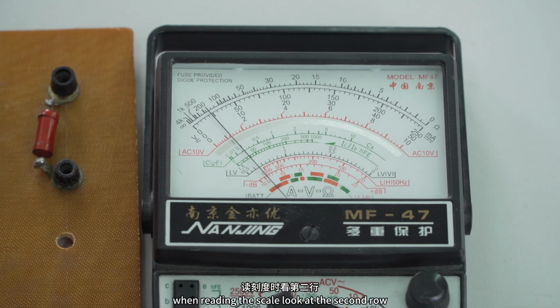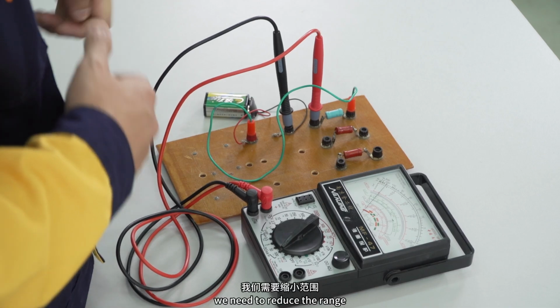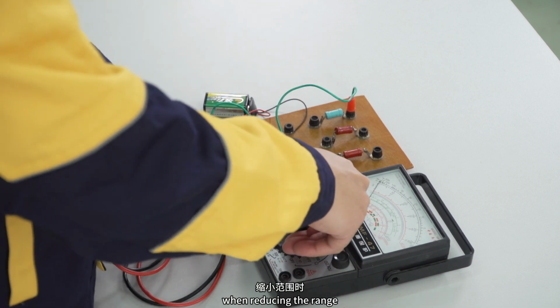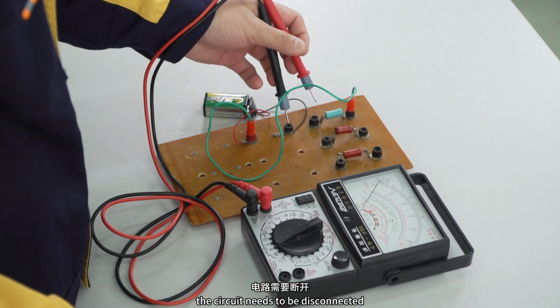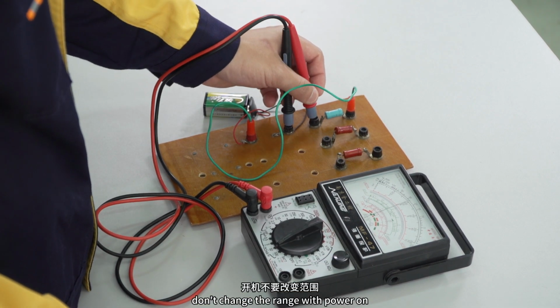When reading the scale, look at the second row. The pointer turns less than 5 scales, so the range is too large. We need to reduce the range. When reducing the range, the circuit needs to be disconnected. Don't change the range with power on.